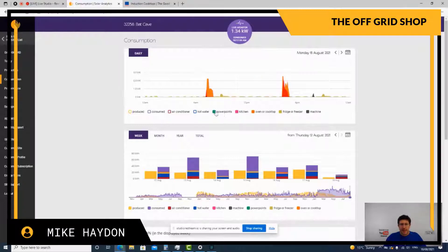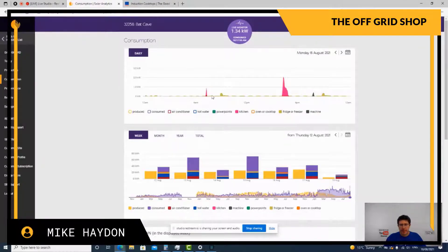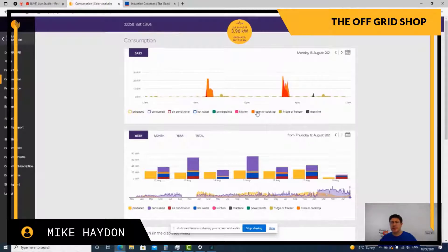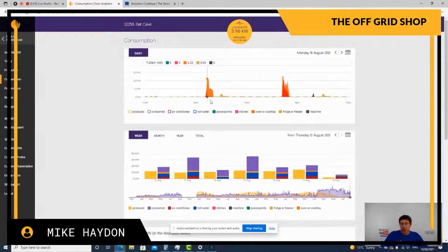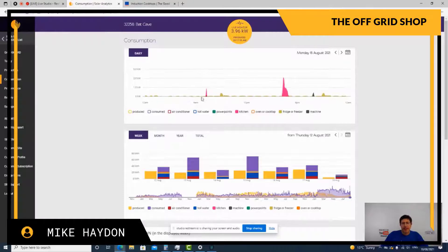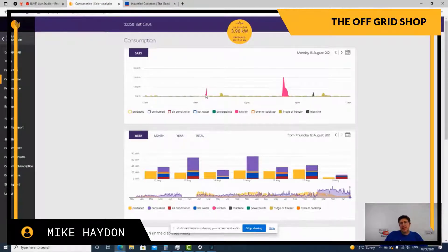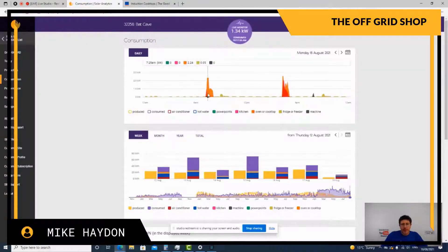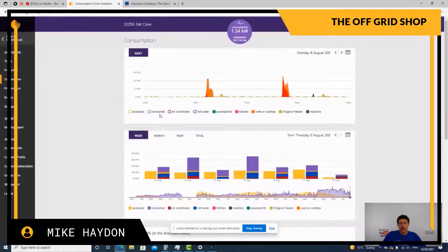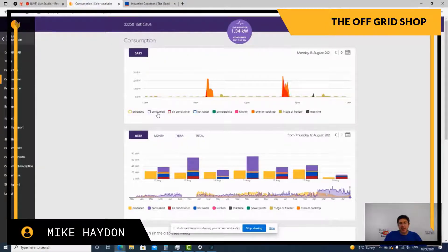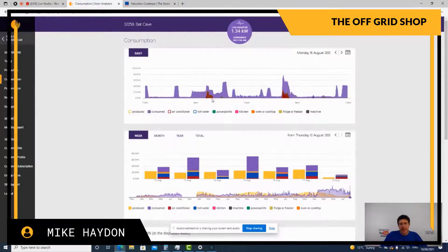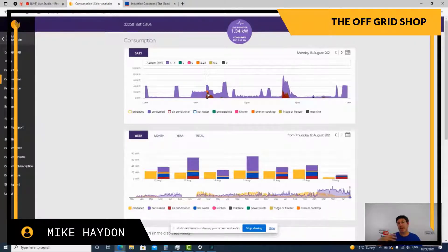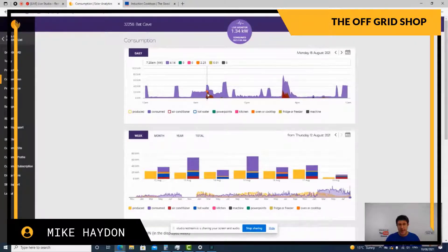Now, the thing to consider here, I'm going to get rid of the oven cooktop for a moment. That is the kitchen. So I'm pretty sure that's our induction cooktop. So something was turned on at the same time. So you can actually see something was turned at the same time. So that's actually just a thousand watts itself. And then the oven cooktop, that's another 2000 watts. So we take on the whole consume there, as you can see, it really jumps up. Because in that moment, even though the cooktop was pulling 1000 watts, the oven was pulling 2000 watts, the rest of the house is pulling 4000.